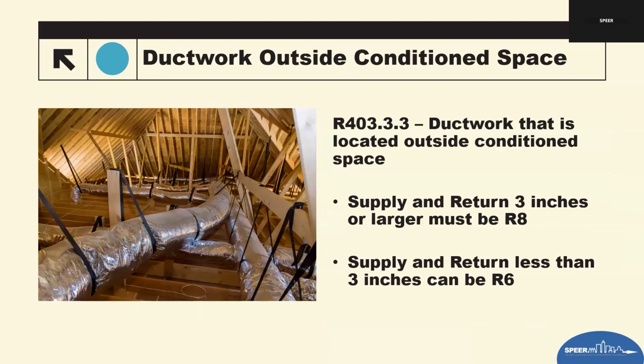Now, ducts outside of the conditioned space. This basically stays the same from 2021. Ducts located outside of conditioned space are most commonly in vented attics, crawl spaces, basements, and garages. Whenever ducts are outside the thermal envelope, the insulation requirements become very important because ducts are exposed to extreme temperatures. We know that in Texas is a lot. The main requirement is that any ducts over 3 inches in diameter must be R8. This goes for any pathway: prescriptive, performance, or ERI. There are still other above-code programs like Energy Star that can vary this depending on how it's being designed, but this is just what the IECC states.